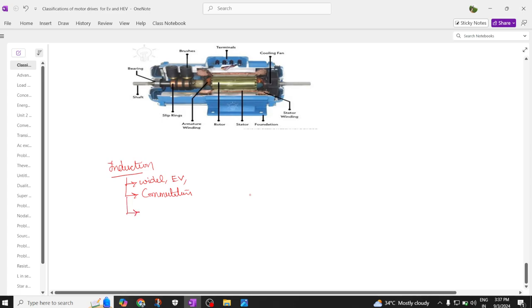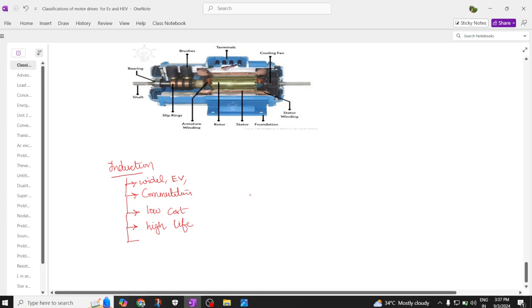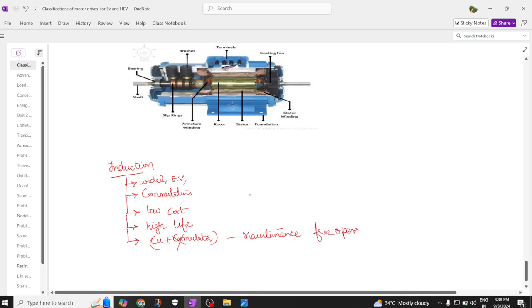Why this induction motor is preferred is basically these induction motors are of low cost. Second, this induction motor doesn't have carbon brushes and commutator, so they have more life and more reliability. Since there are no carbon brushes and commutator, these are called maintenance-free motors — since these two are not used, they are maintenance-free operation motors, so no need to maintain regularly.